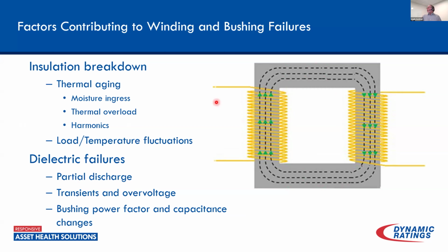So really, when it comes to the GSUs, in these applications we're seeing thermal issues, but it's really the hydrogen that we're seeing in those applications that is due to the partial discharge activity and possibly what's happening with the transients and overvoltages during that switching activity. Whereas with traditional machine-based generation, we may have some thermal, but for the most part, that transformer sits pretty close to the generator, and we might see more mechanical interaction if there were faults on the system and stuff like that.